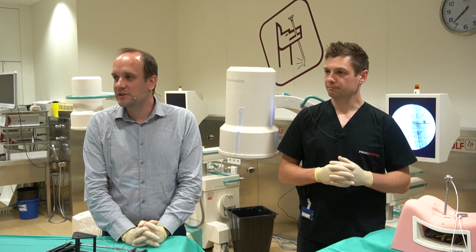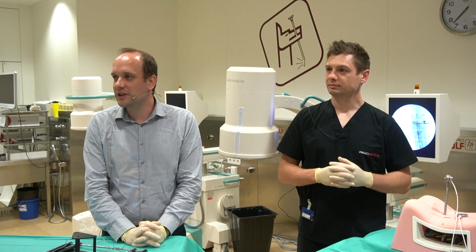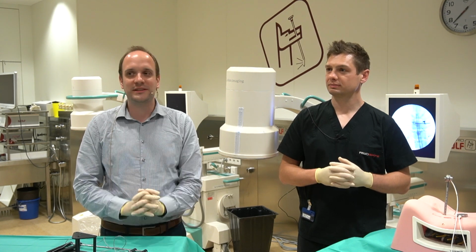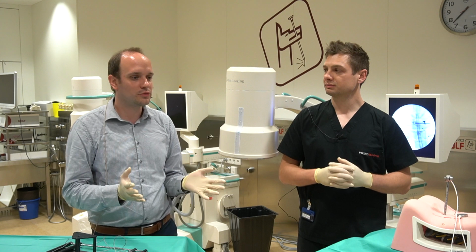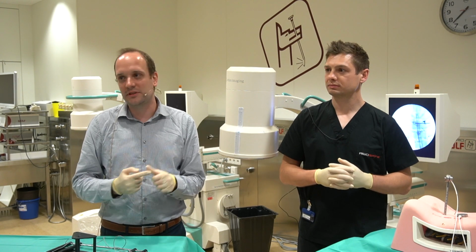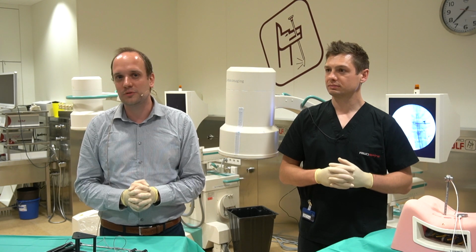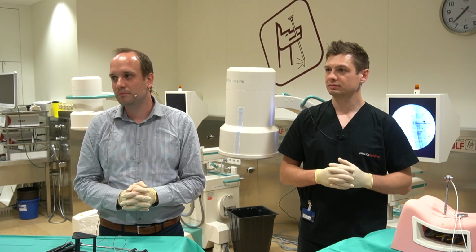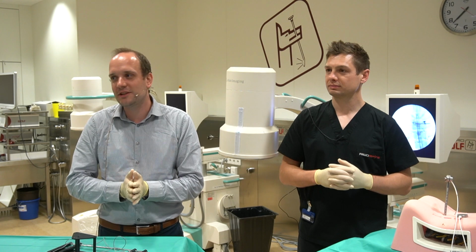Yeah. And then there's the question, how can I do it if there's no connection between the X-ray and the tower? Well, we need some kind of means to transfer the digital image from the C-arm to the system. And we accept the DICOM push, and we accept also the USB transfer as a backup. But of course, we need the digital image in the system somehow.